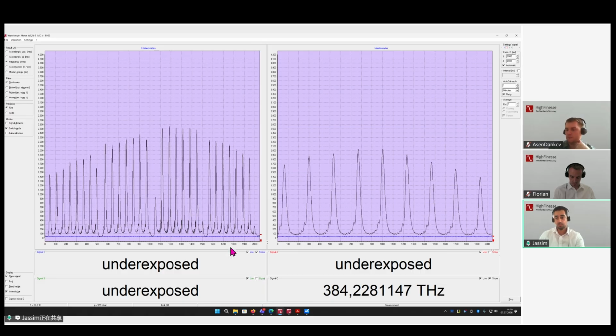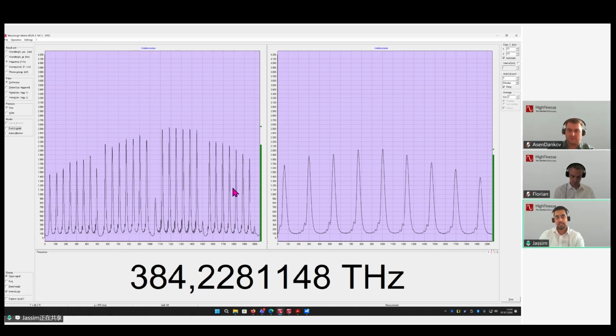Since we are only using 1 channel, we can switch off the switch mode. And you have underneath it the auto calibration option. Now, with the auto calibration option, from the name itself, you can imagine, okay, you want to run your experiment over the weekend or over several days, and you don't want to calibrate your wavelength meter every, say, 1 hour or every few minutes. All you have to do is enable the auto calibration option, and then the wavelength meter itself will calibrate depending on the channel you select for calibration.